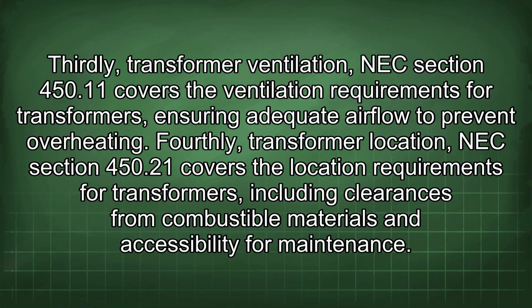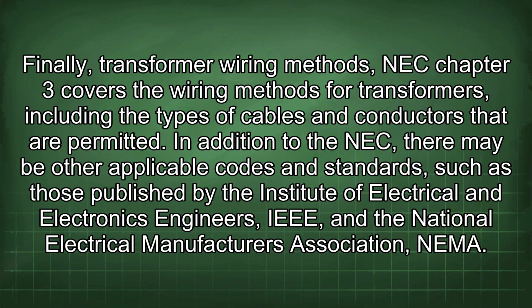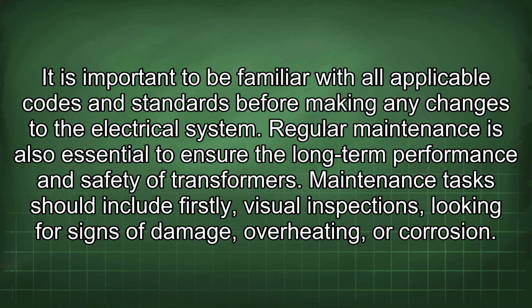Fourthly, transformer location. NEC section 450.21 covers the location requirements for transformers, including clearances from combustible materials and accessibility for maintenance. Finally, transformer wiring methods. NEC chapter 3 covers the wiring methods for transformers, including the types of cables and conductors that are permitted. In addition to the NEC, there may be other applicable codes and standards, such as those published by the Institute of Electrical and Electronics Engineers (IEEE) and the National Electrical Manufacturers Association (NEMA). It is important to be familiar with all applicable codes and standards before making any changes to the electrical system.